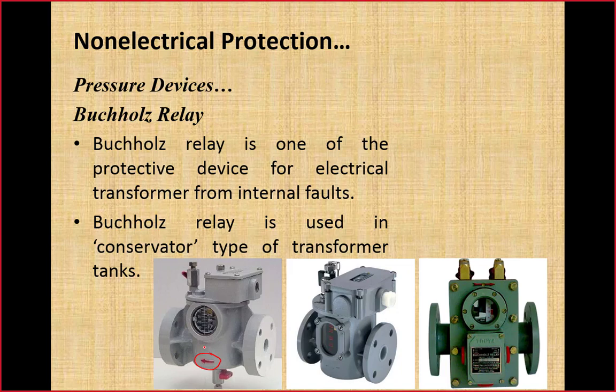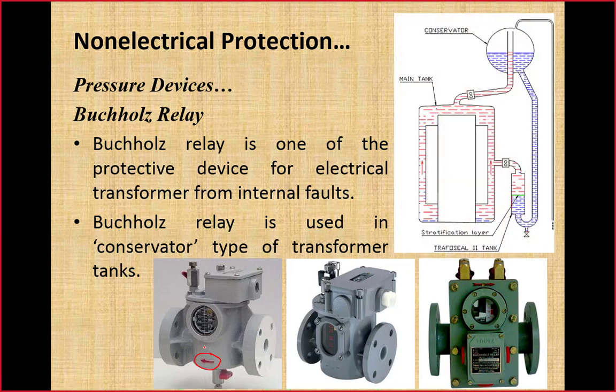Buchholz relay is used in conservator type transformer tank, and here is a transformer tank which has a conservator of oil at the top. So here you can see, as the oil volume reduces in the tank of the transformer, oil will move from this conservator through this path downward into the transformer tank. In case of a pressure wave created within the transformer due to a fault or decomposition of oil, oil will be pushed from the transformer tank into the conservator through this path.